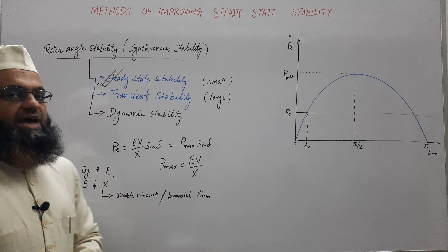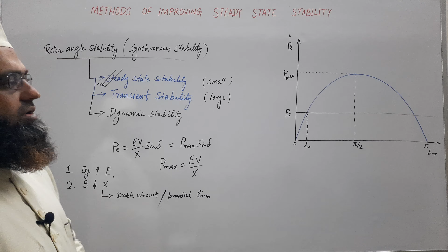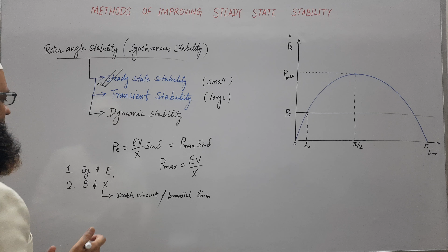So this way, by using a double circuit line, we are reducing X, and hence power transfer capability is improved, that is, the steady state stability limit is improved. Some other advantages are also there by using parallel lines or double circuit transmission lines, like reliability is improved. Even if there is a fault in one of the double circuit lines, the healthy line may be in operation, fine. Next point you may write by using bundled conductors.